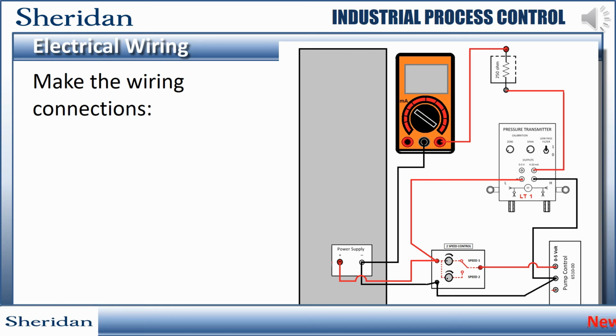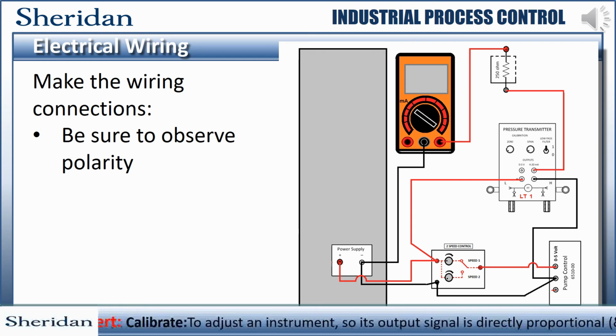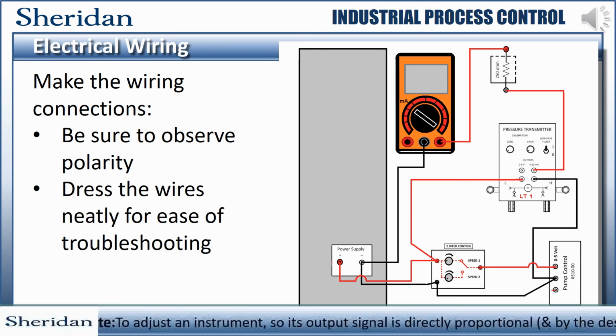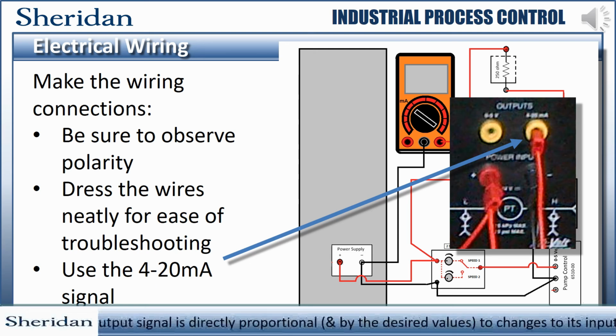Follow the wiring diagram. The one that has been provided has been simplified and does not represent a normal set of electrical prints. Always follow the manufacturer's information, usually provided with the device, and again, if any doubt remains, ask a person in charge or do the research. Transmitters can cost thousands of dollars and are very accurate devices if installed properly. Wiring them incorrectly can do severe damage to them. So always be sure to observe polarity, keep your wiring and terminations neat so that you can double check your work easily, and it makes it easier for future troubleshooting. And always make sure you use the correct wiring method.